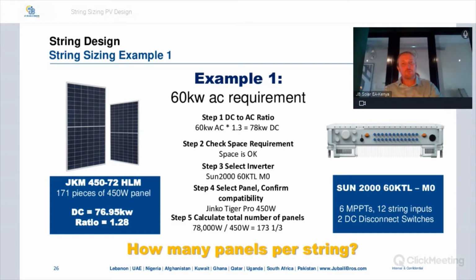Let's go through some examples. So example number one, we have a 60 kilowatt AC requirement. If you look in the center of the screen, we have it broken down, step 1, 2, 3, 4, 5. So step 1, once you know the 60 kilowatt AC requirement, is to calculate the DC to AC ratio. 60 kilowatts AC times 1.3 is 78 kilowatts DC. So we want approximately 78 kilowatts DC.